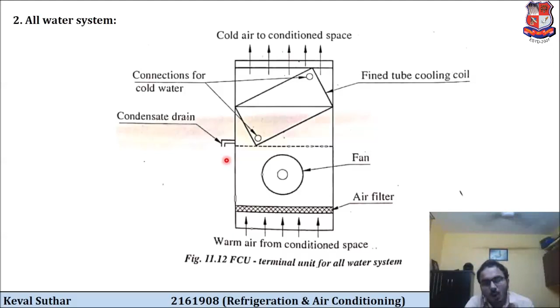Now the next topic is the air water system, in which we will be having a combination of all air system and all water system. As you can see here, we are having two central plants. The first central plant is for primary air. From this supply duct with fan, the primary air is going into this terminal unit, and then it is returning back here. This primary air is doing the task of cooling. At the bottom we are having the secondary plant, the central plant for secondary water. Here we are having a supply line with pump through which the secondary cold water is coming here. It is doing the task of cooling, and then this secondary water is returning back into the central plant for secondary water. From the bottom the primary air and secondary air is coming and passing through this conditioned space, and from the top secondary air is again returning into this terminal unit. This is the way the air water system is working.